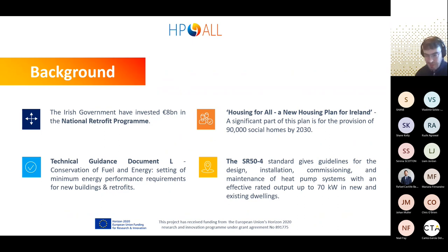Another important document is guidance document L, or Part L, on the conservation of fuel and energy, which sets a minimum energy requirement for new builds and retrofits. This is why heat pumps are so heavily pushed in Ireland, because to reach these energy performance requirements it's commonplace to use a heat pump. Then there is the SR50-4 standard, which gives guidelines for design, installation, and commissioning of heat pump systems up to 70 kilowatts, for new and existing dwellings, so for a new build or for retrofits.